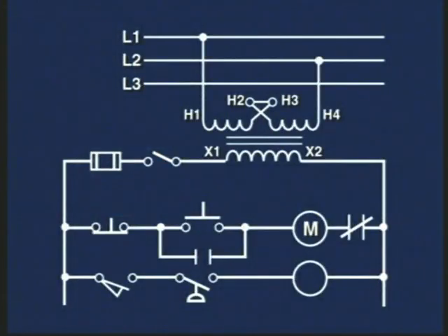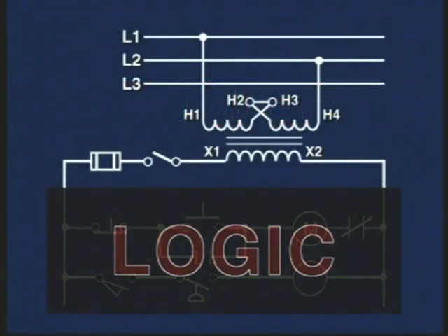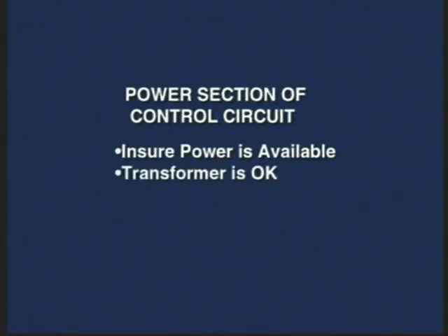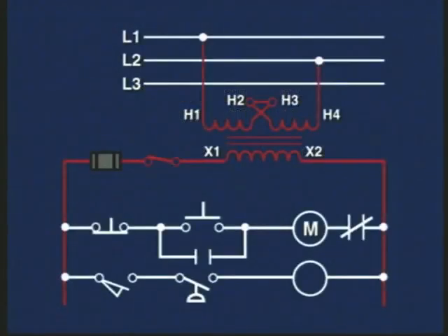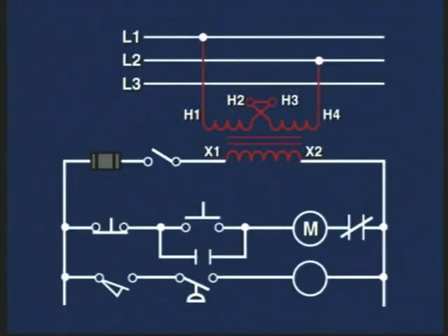In a control circuit, there are two main areas to investigate, namely the power section of the circuit and the logic section, or the ladder circuit part. The power section of the control circuit must be checked to ensure that incoming power is available to the circuit and that the transformer is operating correctly. To perform this check, we first disconnect power to the ladder circuit so that, if a short was the problem, it cannot occur during this check.